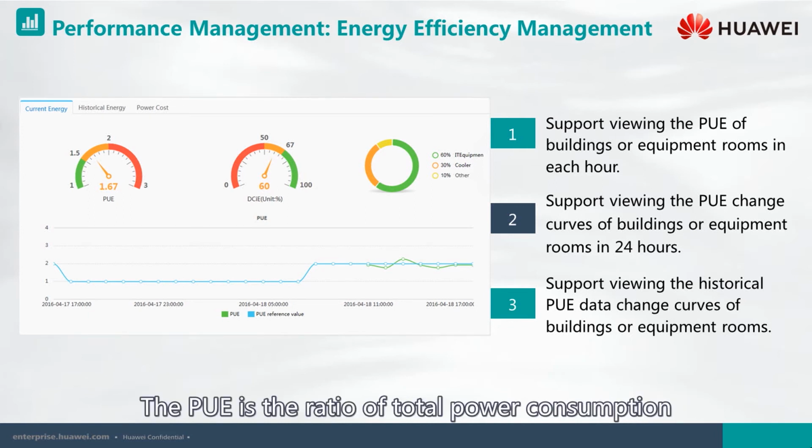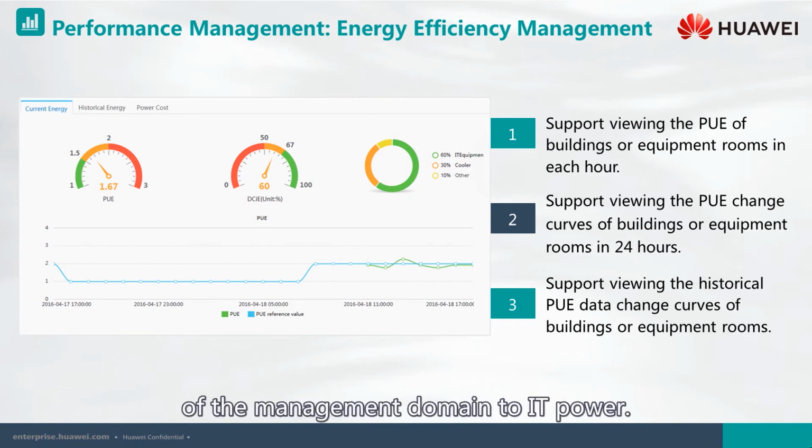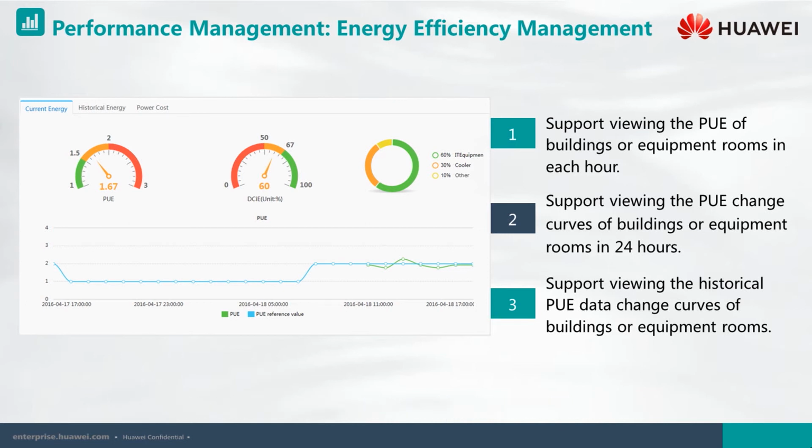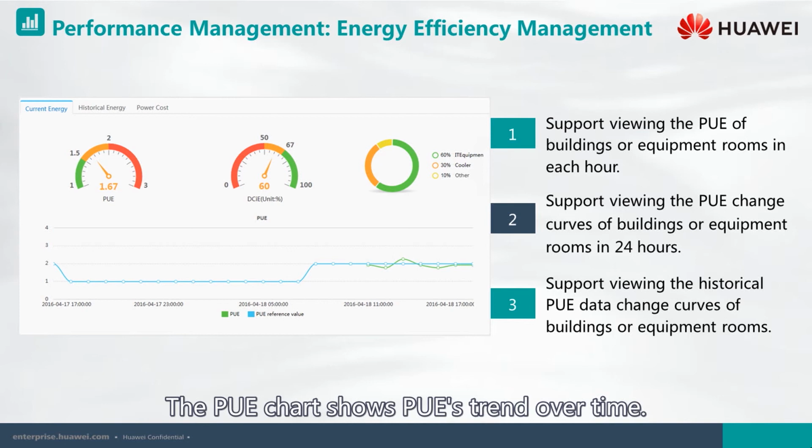The PUE is the ratio of total power consumption of the management domain to IT power. The DCIE value is the reciprocal of the PUE. The PUE chart shows PUE's trend over time.